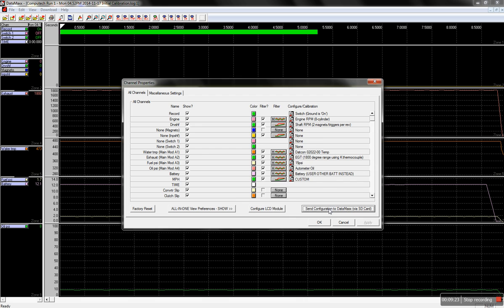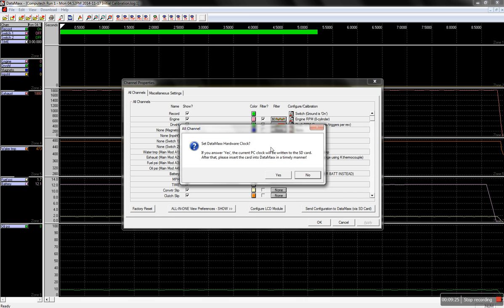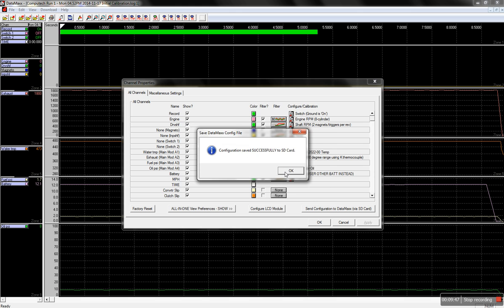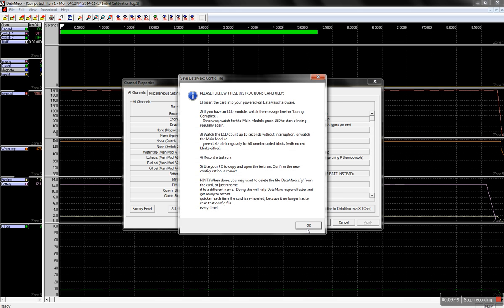So hit send config to Datamax via SD card. It's going to ask you if you want to set your hardware clock. If you are close to your Datamax data logger, then we can say yes. If you are not, then say no. Essentially, the SD card has no internal clock. So for every second it takes you to get over to the car, that's a second it does not know has passed. So if you wait 5 minutes, your clock's going to be 5 minutes slow. I'm pretty close. I'm going to go ahead and say yes, and then hit OK, and OK.